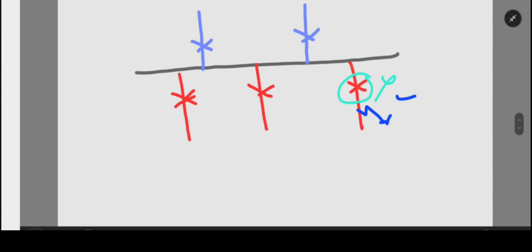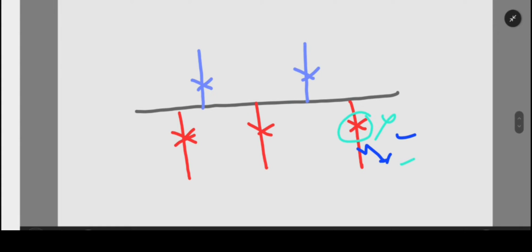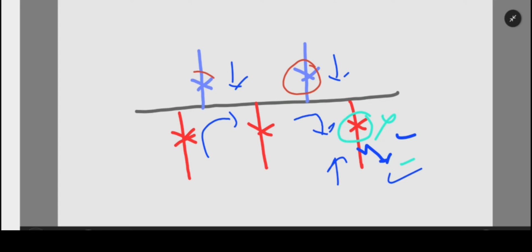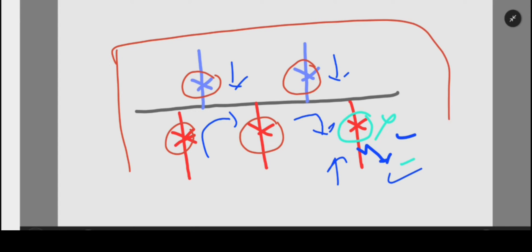If the fault happens there, the fault current will flow from multiple directions — this direction, this direction, and this direction. So if the fault happened there, all breakers associated with the fault will trip. The LBB will give a trip command to all the breakers and will shut down the entire single bus.